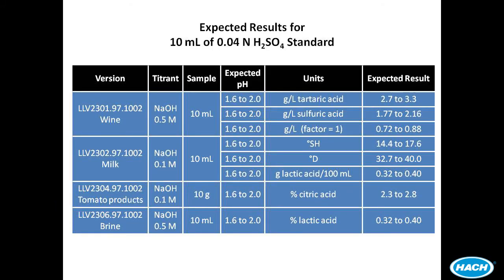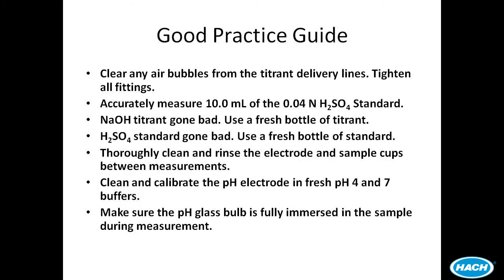The expected result depends on your model and units. This table shows the expected range of results for each model and unit. If your result is not within the expected range, you should first try repeating the titration. The most common cause of error are loose fittings and standards that have drifted outside the acceptable range.